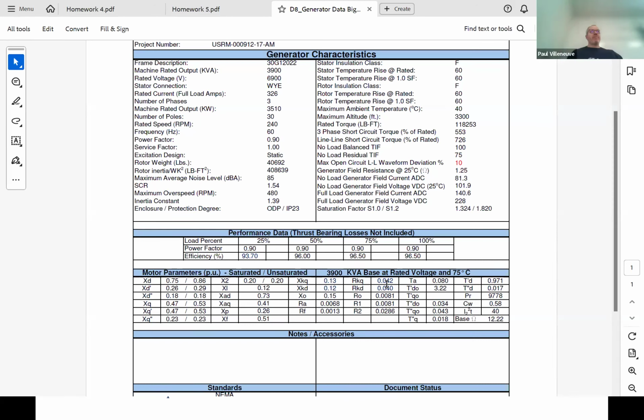Yes, sir. What is the service factor? Anybody want to guess the service factor? It's another way to say quality of the motor or the machine. If something is rated for a 1.15 service factor, and the nameplate, in this case, says 4 megawatts, you could actually run it at 1.15 times its power output and it would still work. So it's a way of saying this is a higher quality built application because it's designed to run at more than 4 megawatts. It's rated for 4 megawatts, and that's what you should run it at. But it actually has a little bit more copper in it, perhaps a little better cooling, so you can get more power out of it if you need to.